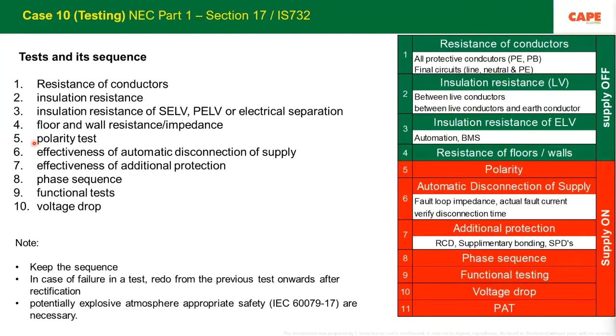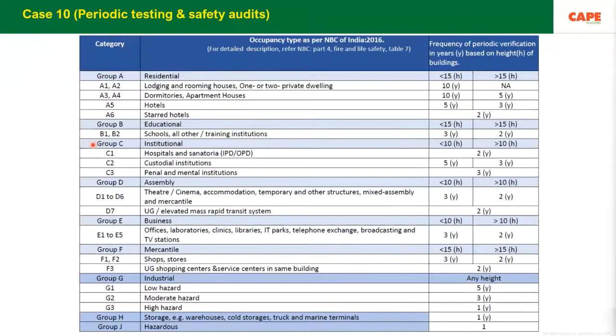The last one is, I would say, the testing of an electrical installation. There are 10 tests. Of course, there is one more, which foreign countries started doing, called PAT, Portable Appliance Test. These 10 tests, or at least the 10 tests, are made mandatory in the regulations or in the standards. But unfortunately, you have to be careful, and you should do this particular thing. So case number 10 is testing of the electrical installation, also the periodic testing. In a periodic testing, you probably don't need to do all the tests, but some of the tests are mandatory.